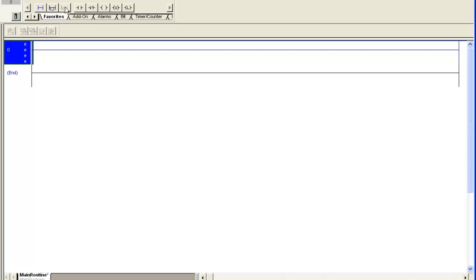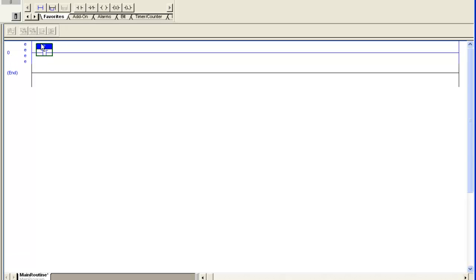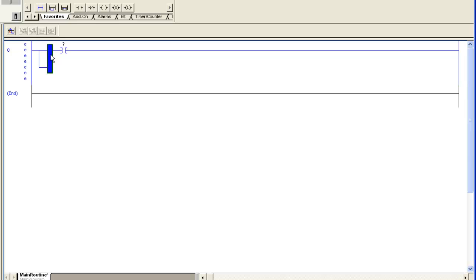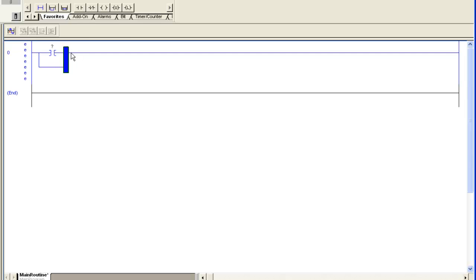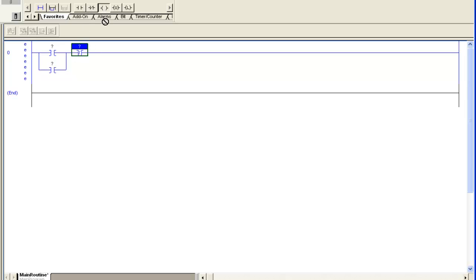So what I'll do is I'll start dragging some instructions down. Put a branch in. What I'm making here is a simple seal-in circuit where I have a start push button, a stop push button, and a little latch bit.